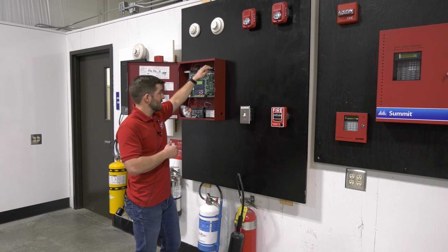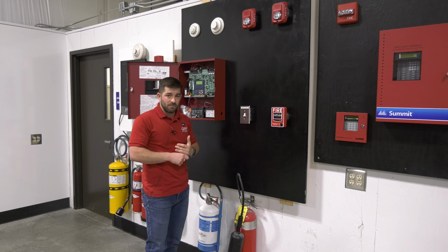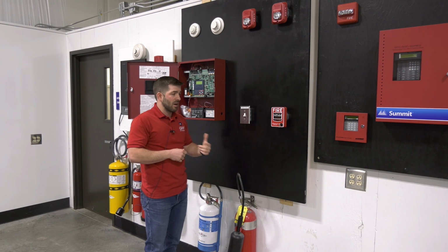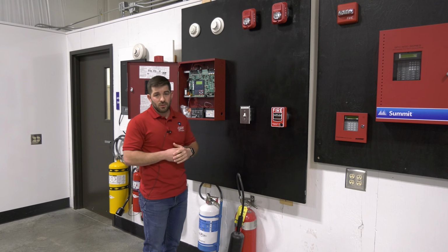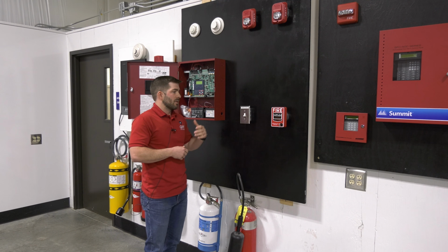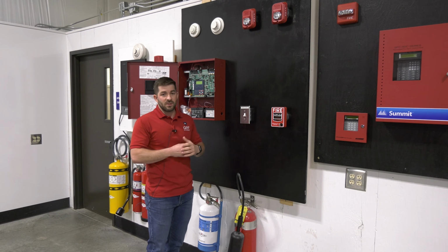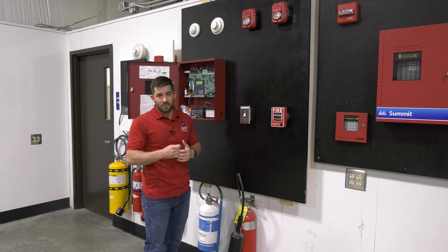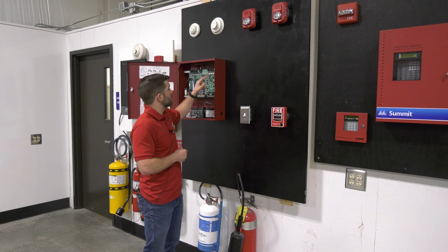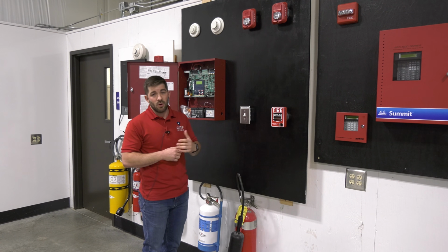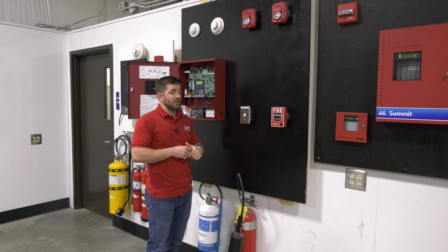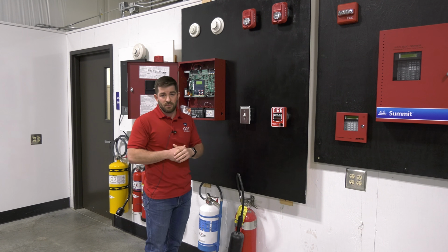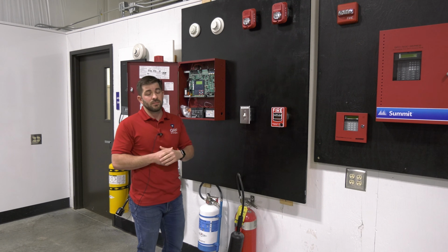Now, in this instance, it's only going to give you a general alarm, a general supervisory, or a general trouble. It's not going to be able to give you the contact ID reporting and tell you there's a NAC 1 trouble, there's a NAC 2 trouble, alarm module 4 second floor. It's not going to give you that distinct information, but it will monitor the alarm, trouble, and supervisory relays on your panel. So when it goes into alarm, it closes that circuit, creates a short, and then it reports the alarm. Supervisory, trouble, same thing.